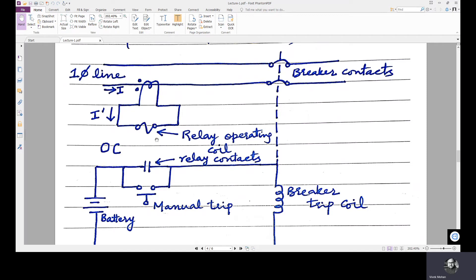Now the function of the relay. The role of the CT is over in the sequence of events — the fault has occurred and the CT has done its role. The function of the relay is to discriminate between normal and faulty operating conditions. The overcurrent relay has an operating coil connected to the secondary CT winding and a set of contacts. When the magnitude of I dash — the secondary CT current — exceeds a specified pickup value, some threshold value I dash threshold, the operating coil causes the normally open contacts to close. This completes the circuit, energizes the breaker trip coil, and the breaker contacts are opened, isolating the system.